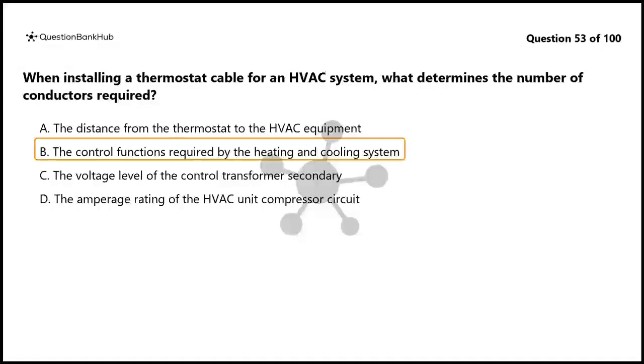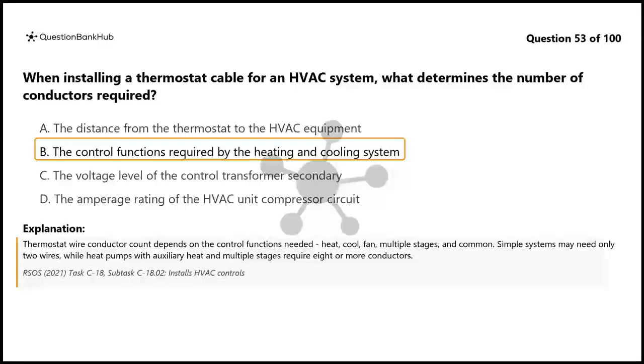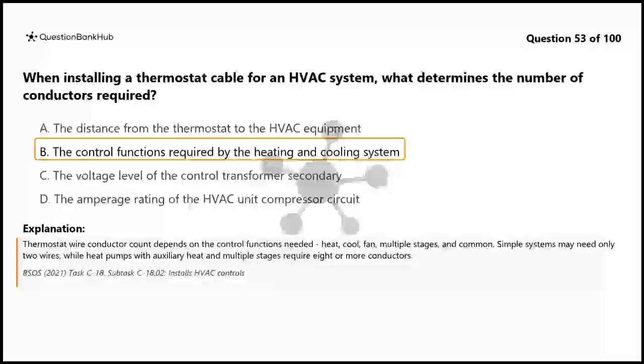The correct answer is B. The control functions required by the heating and cooling system. Thermostat wire conductor count depends on the control functions needed: heat, cool, fan, multiple stages, and common. Simple systems may need only 2 wires, while heat pumps with auxiliary heat and multiple stages require 8 or more conductors.